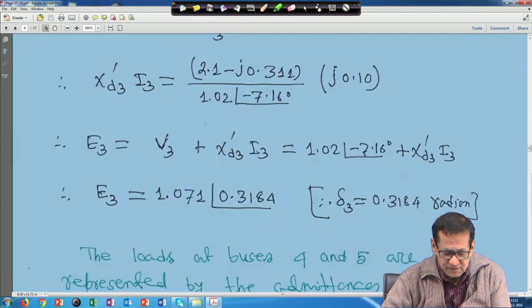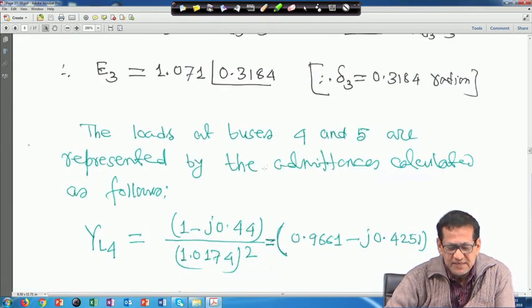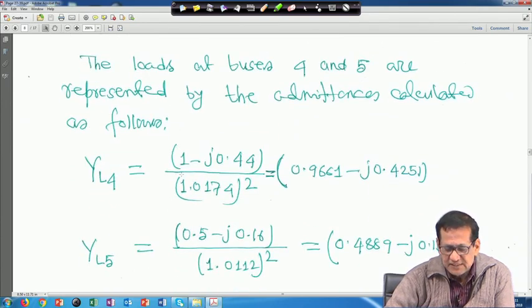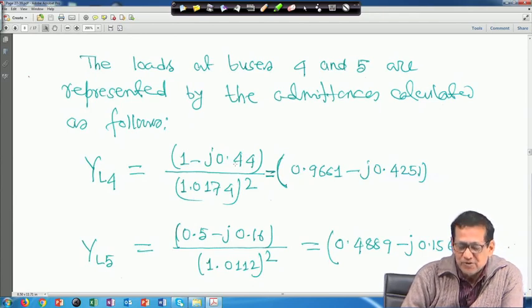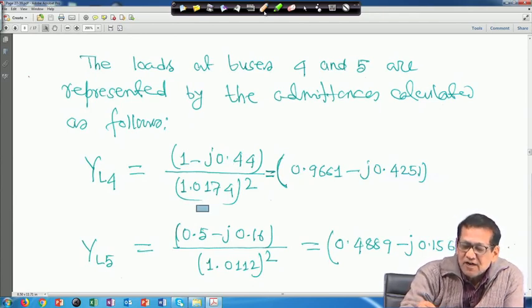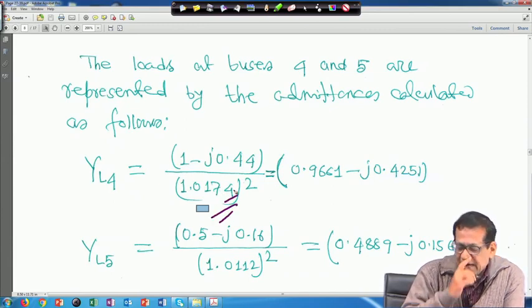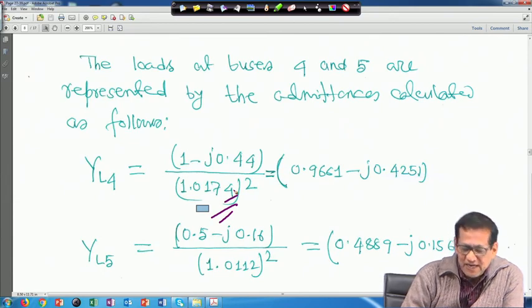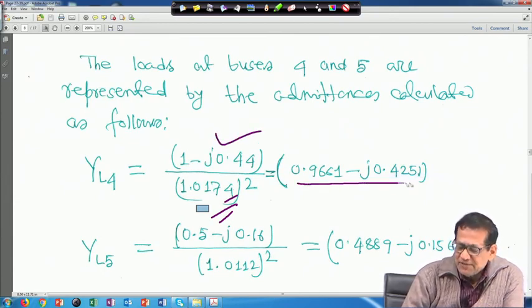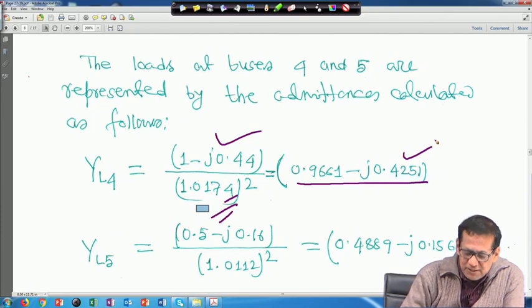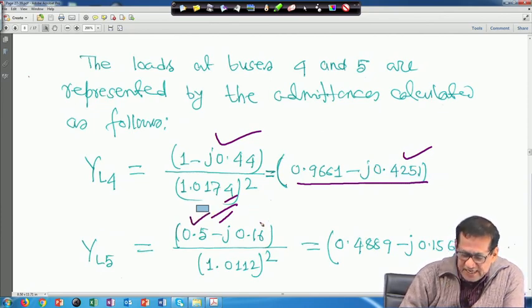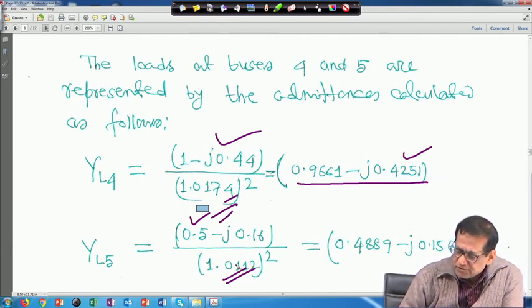The loads at buses 4 and 5 are represented by admittances calculated as follows. At bus 4, the load admittance = (1 − j0.44) / |V4|². At bus 5, similarly, (0.5 − j0.16) / |V5|² where |V5| = 1.0112. These load admittances are treated as shunt elements in the Y-bus matrix.